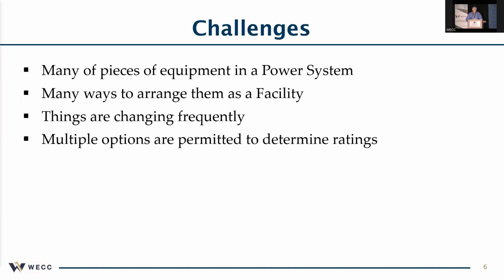And then things are changing frequently. Maybe not for a really small system, but for large systems, there's always projects going on. There's always upgrades. There's damage. A transformer gets replaced. Transformers have a long lead time, so you borrow a transformer or get a transformer. What are the odds it's going to be rated exactly the same with the same cooling capacity? Maybe, but maybe not. So how do you account for all these changes that are going on and keep your facility ratings documents alive so that they remain accurate?